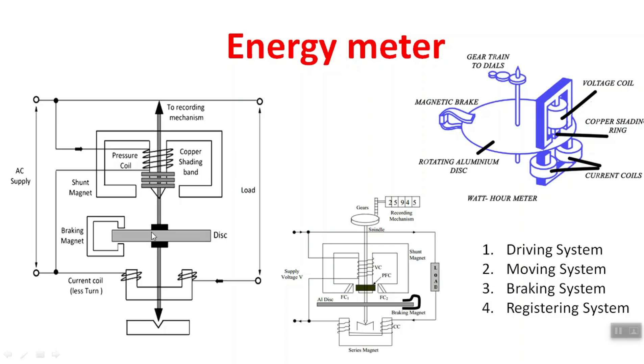The two magnetic fields from the pressure coil and the current coil oppose each other and create a combined rotating field on the aluminum disk. The copper shading bars help convert the magnetic field of the pressure coil by 90 degrees. These adjustable copper bars shift the magnetic field by 90 degrees, creating the phase difference needed to rotate the disk.